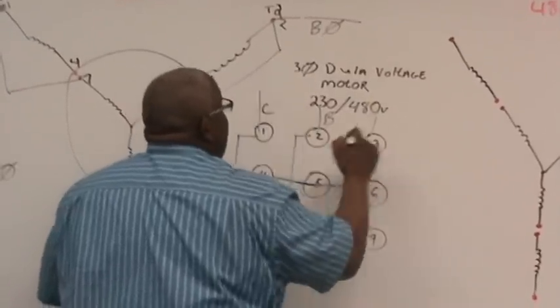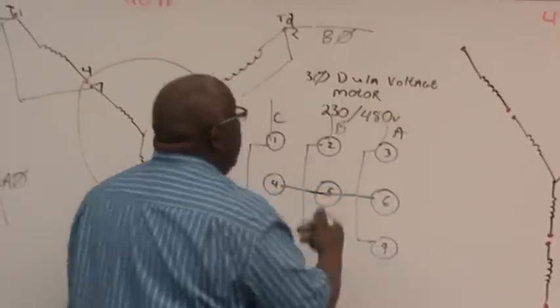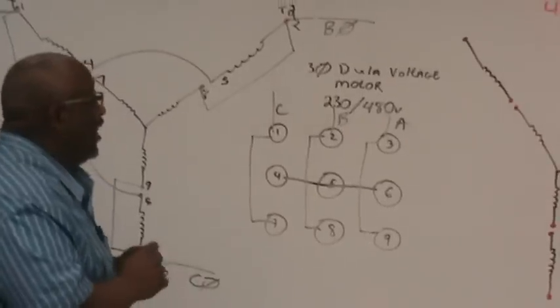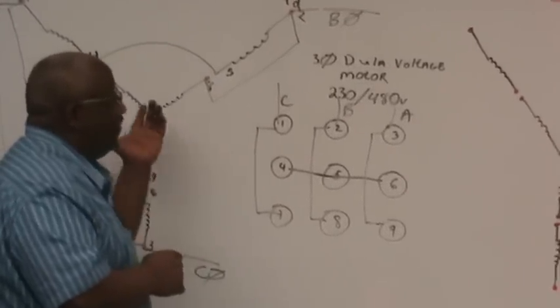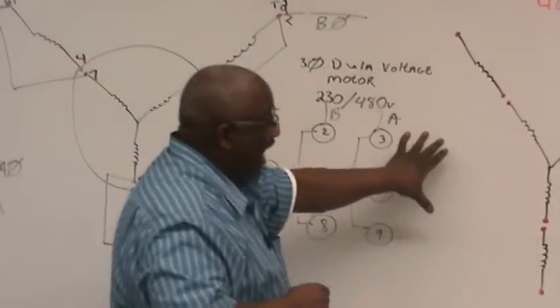Typically, we'll swap C with A, and this will provide us with a counterclockwise rotation. Now, our windings are in parallel, and that's for low voltage. But what if we need high voltage?